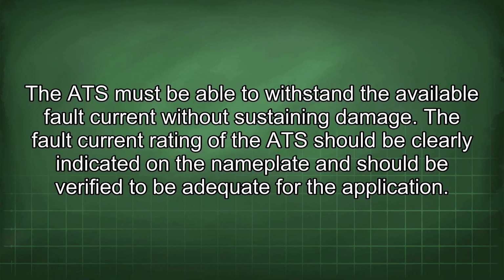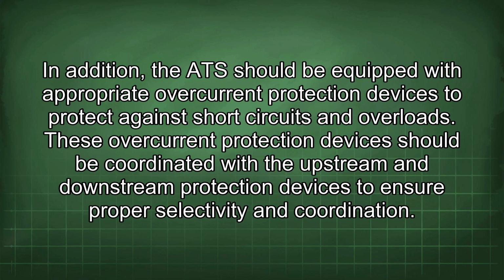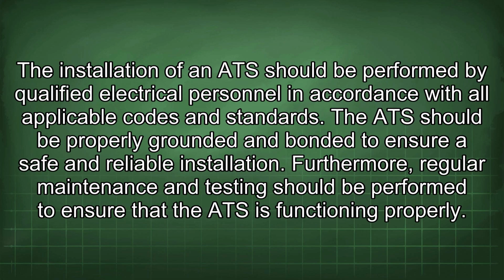adequate for the application. In addition, the ATS should be equipped with appropriate overcurrent protection devices to protect against short circuits and overloads. These overcurrent protection devices should be coordinated with upstream and downstream protection devices to ensure proper selectivity and coordination. The installation of an ATS should be performed by qualified electrical personnel in accordance with all applicable codes and standards. The ATS should be properly grounded and bonded to ensure a safe and reliable installation.